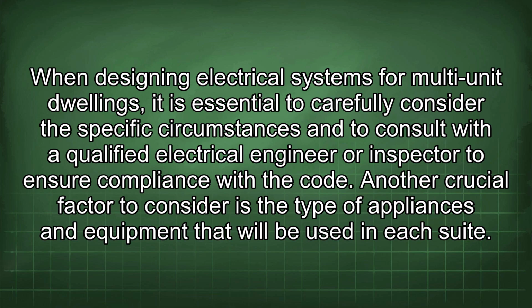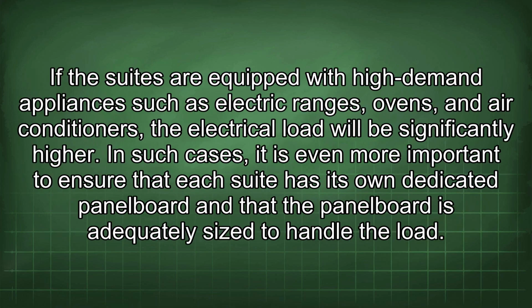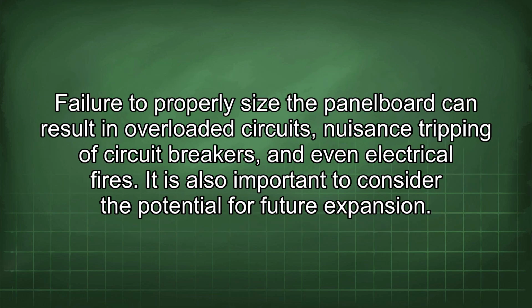Another crucial factor to consider is the type of appliances and equipment that will be used in each suite. If the suites are equipped with high-demand appliances such as electric ranges, ovens, and air conditioners, the electrical load will be significantly higher. In such cases, it is even more important to ensure that each suite has its own dedicated panel board and that the panel board is adequately sized to handle the load. Failure to properly size the panel board can result in overloaded circuits, nuisance tripping of circuit breakers, and even electrical fires.